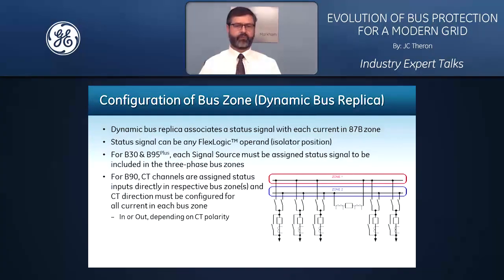Let's have a look at the configuration of the bus zones, specifically for dynamic bus replica. Now, each feeder or current has to have a status signal to associate it with the bus zone specifically. And the status signal can be either a FlexLogic operand.